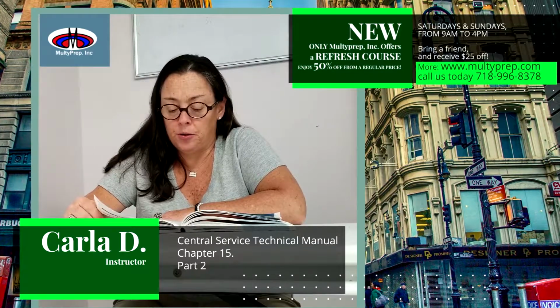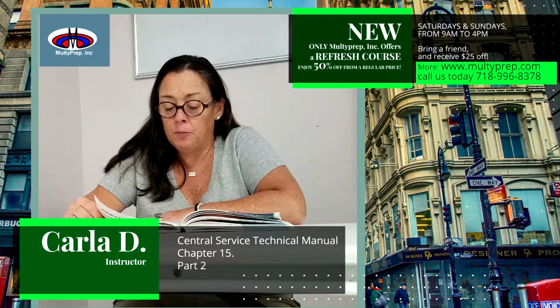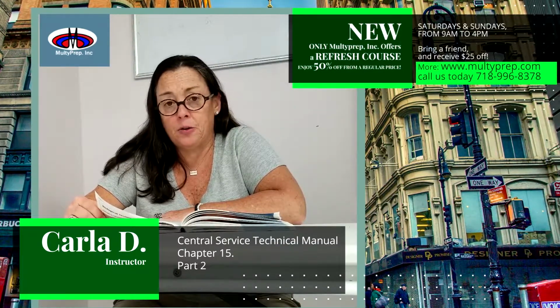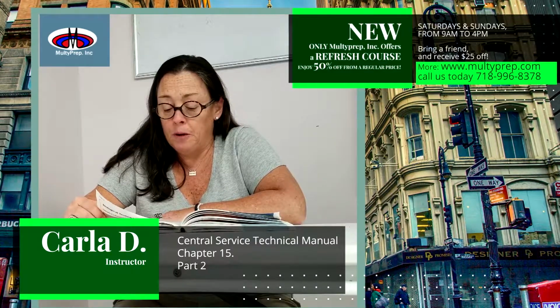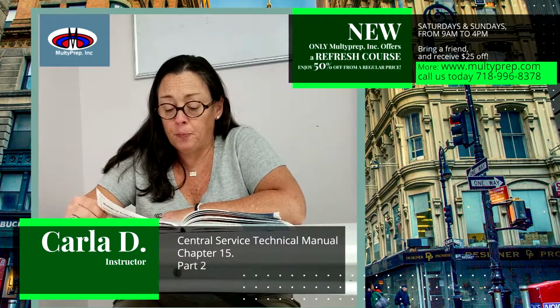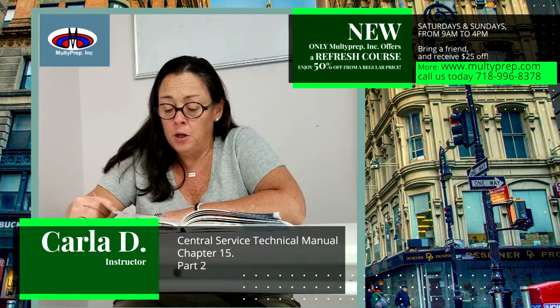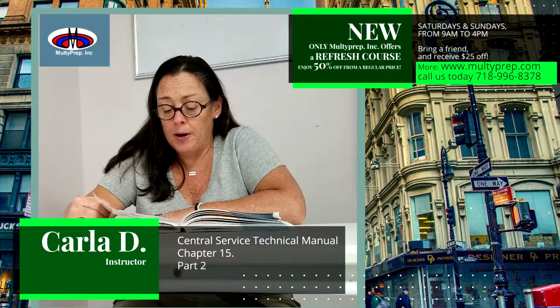Loading and unloading ethylene oxide sterilizers. ETO sterilizers must be properly loaded for effective sterilization. Overloading impedes proper air removal, load humidification, sterilant penetration, and aeration. Items should be arranged to avoid contact with chamber walls. Pouches should be placed on edge in the wire baskets. Stacking one package on another should be avoided.